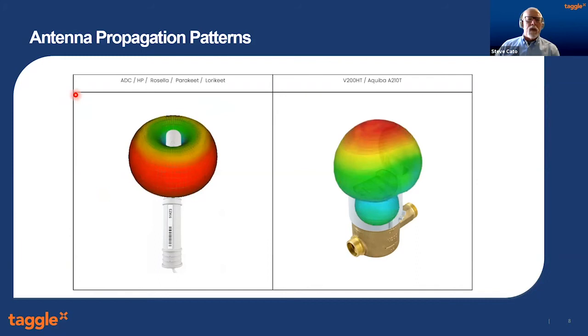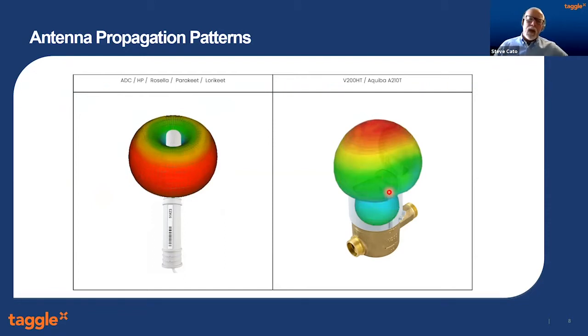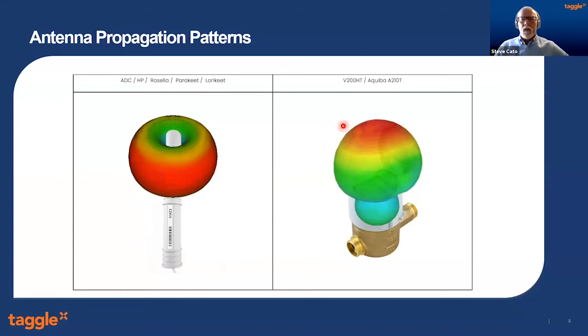If your receiver is over here, it's only going to see the radio bouncing that way — so you've got a maximum of about 50% of your power. With the integrated meters — the V200HT and the Aquibas — it's a different shaped antenna, so propagation is different. They're organized so that the majority of the power is coming up out of the top of the meter, which is the best position to maximize the amount of energy going towards the receiver.